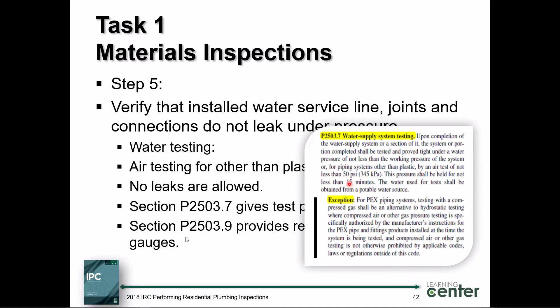There you have it right there. If the piping or tubing is other than plastic, and if I tested it by air, not less than 50 psi. You have to be careful with plastic piping, ladies and gentlemen, don't you? What happens if I used, I don't know, like PVC, and I applied an air test to PVC? Maybe I'm a plumbing contractor. I've been doing it for 50 years, and I'll say, I'll show that new plumbing inspector that I don't have any leaks. I'll pump that thing up to 500 psi. What do you think will happen to PVC pipe under that type of pressure, ladies and gentlemen? Failure. It will explode, right? And the shards and the shrapnel will injure people and cause a lot of damage, bad stuff.